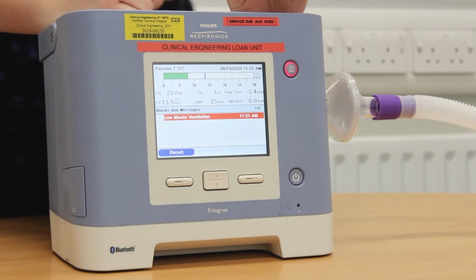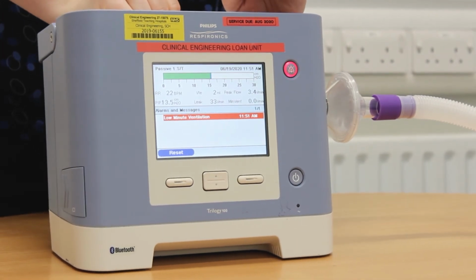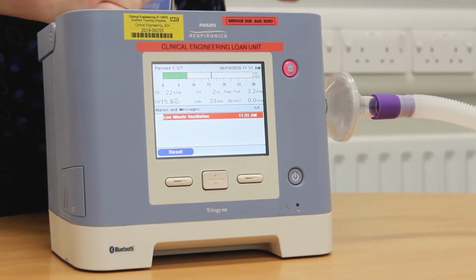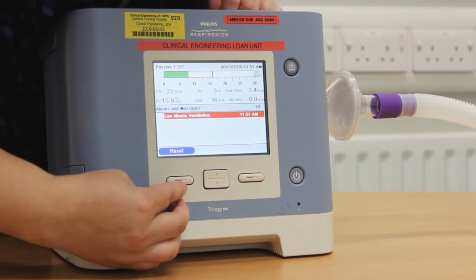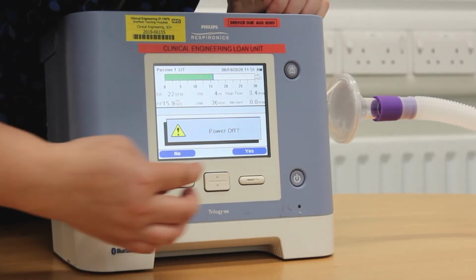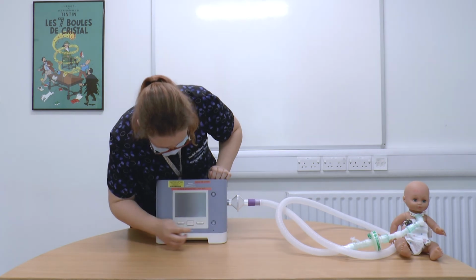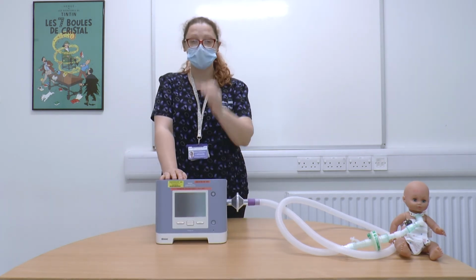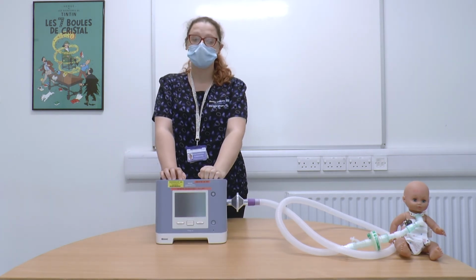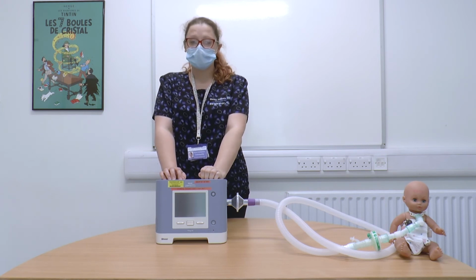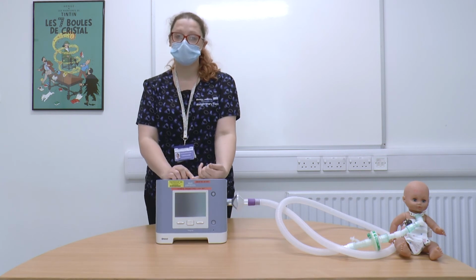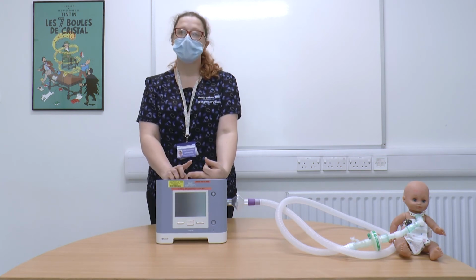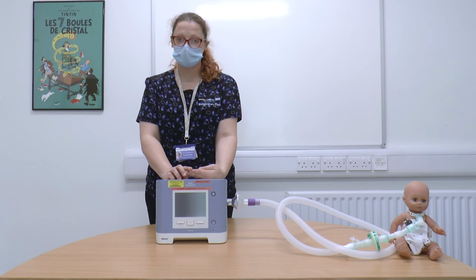Any alarm that goes off, you check the child first. You then work your way back from the child to the machine. I'm just going to go through what those alarms can mean. They come up either as a red alarm, telling you it wants you to immediately do something, or a yellow alarm. A red alarm can either be low minute volume, low tidal volume, low respiratory rate, apnea.